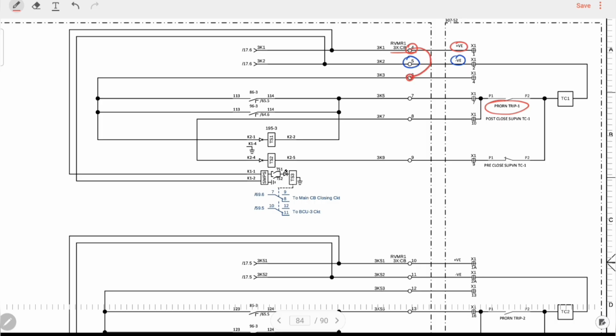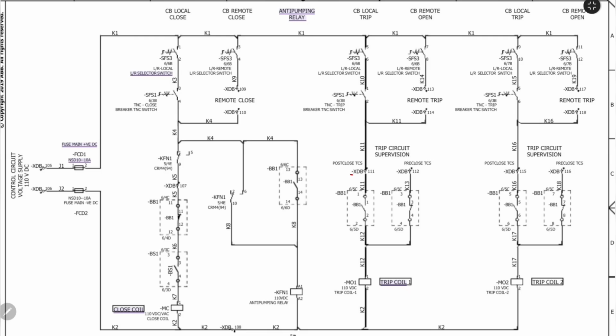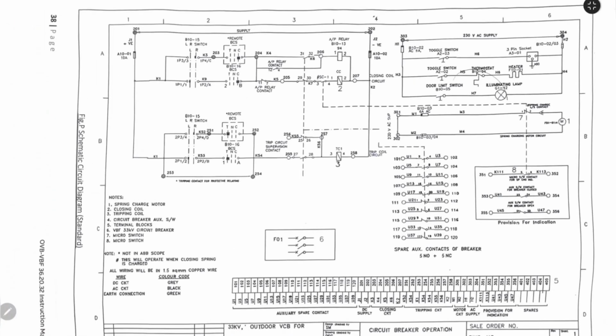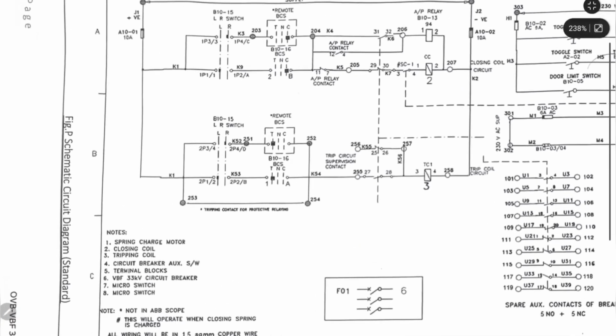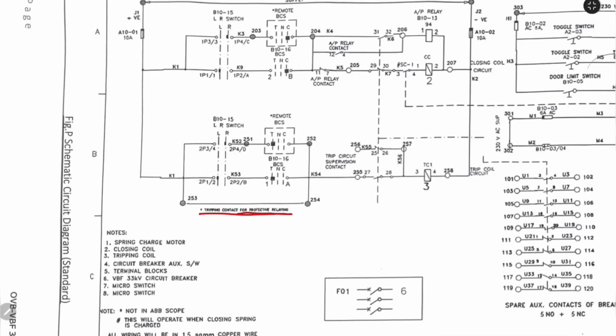When master trip relay 86 or 96 operates, its contact closes and extends the DC positive to Siemens terminal 3xCB7. From here, wire Siemens terminal 3xCB7 to the breaker's protection trip interface terminal exactly as shown in the approved project schematic. In many ABB VCB configurations, this interfaces through terminal XDB111. However, terminal assignments may vary depending on the breaker model, customer specification, or project design. Always verify the manufacturer's manual and the approved wiring drawings before commissioning.